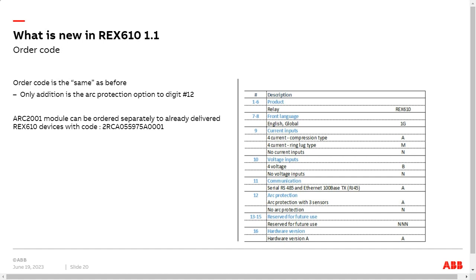And for example, as I did in my case, I have a 1.0 firmware device without the ARC protection. So I ordered an ARC module separately using that code, which is on the screen, this 2RCA code. And then I added it to the device, and after that I added the new 1.1 firmware and did the migration of the configuration. I also told in this hardware configuration tool that I now have the ARC module installed. And after that I could take the ARC protection into use in my own personal REX610 here at home.